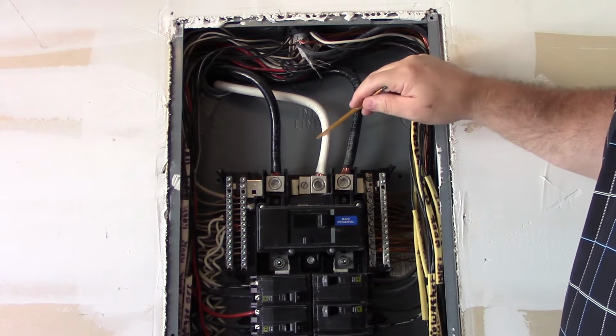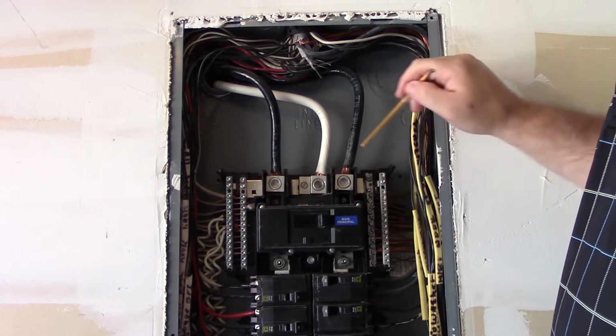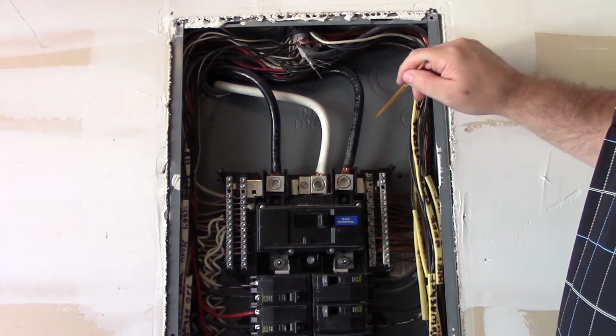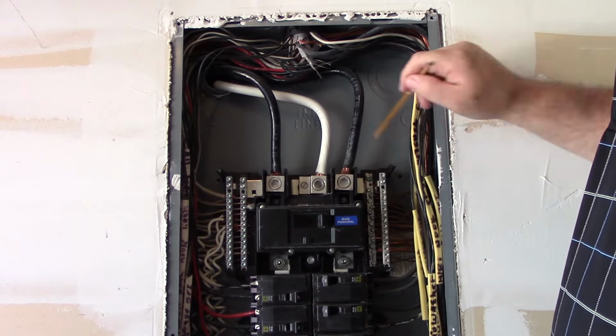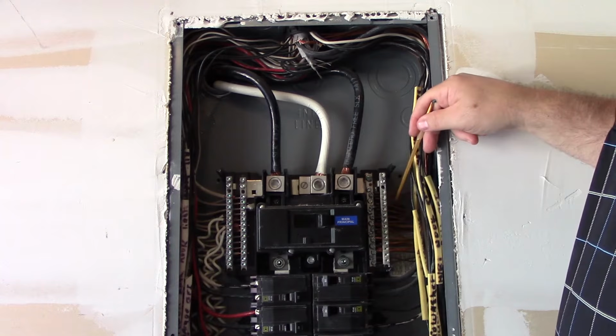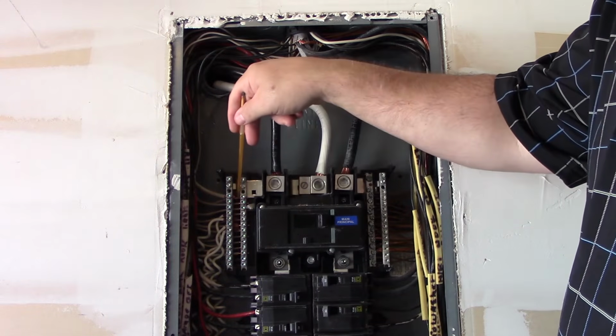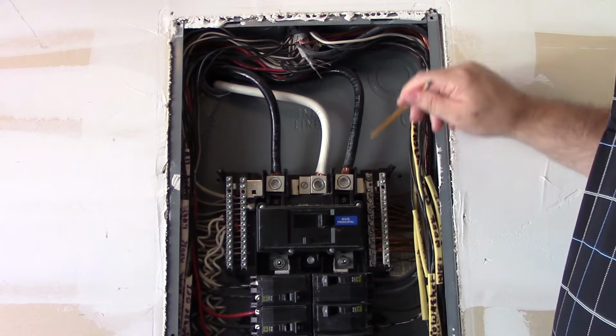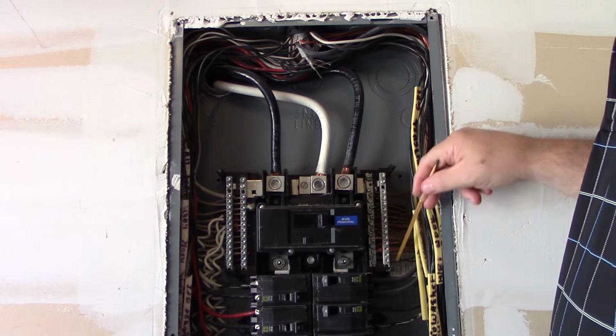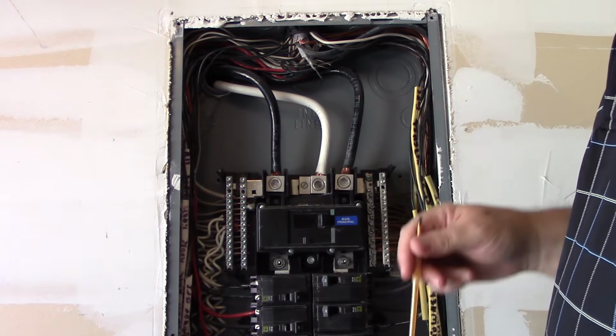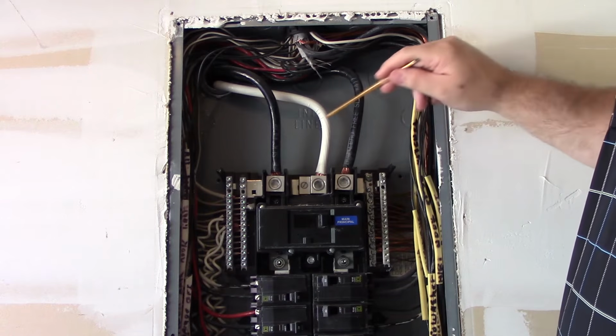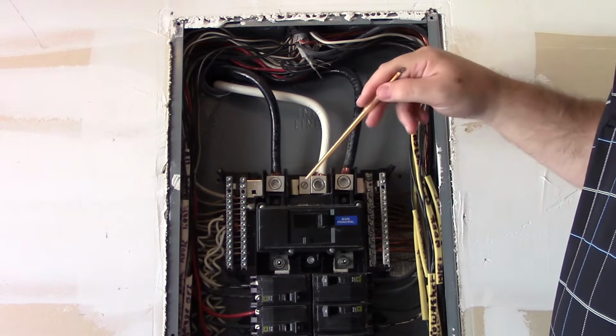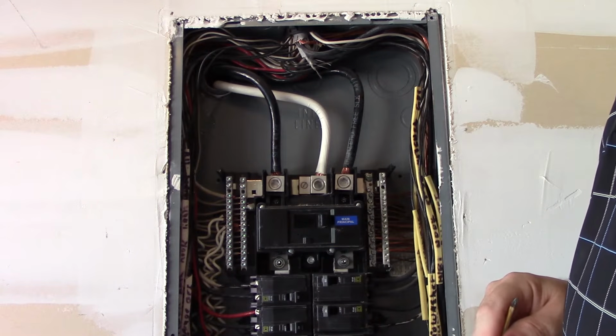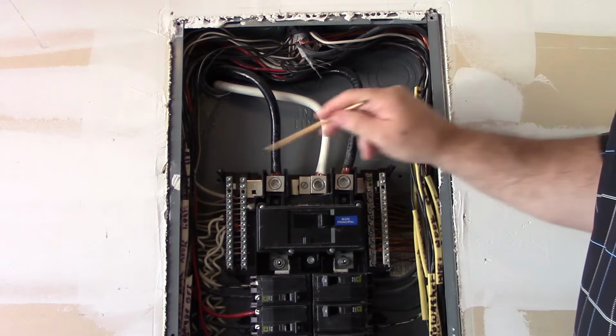So I have to connect the grounded conductor and its associated bus bar to the actual metal cabinet, so that when I bring equipment grounding conductors in and my grounded conductors in, they connect to the same common bar that's also connected to the enclosure. In case my enclosure gets energized, we want this equipment grounding conductor to allow fault current to come back, get to here, and get back to the grounded conductor to complete that cycle to allow these overcurrent devices to operate correctly. All right, so everything is connected together.